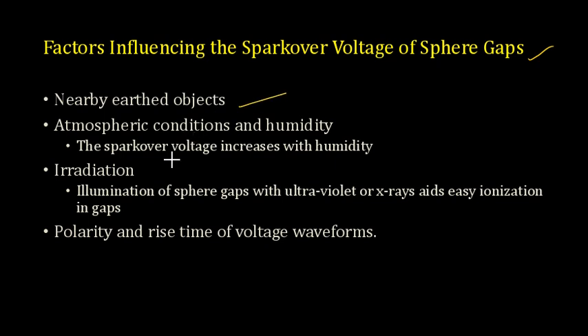Now atmospheric conditions and the humidity will affect the sphere gap voltage. Your spark over voltage will increase with humidity. So as the humidity increases, there are chances that your spark over voltage will increase, and the increase is something like this. So this is your humidity, and this is spark over voltage.